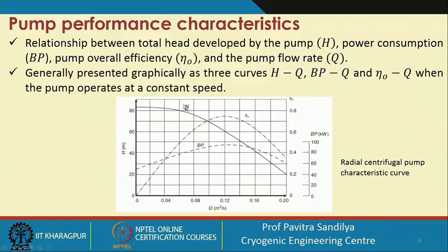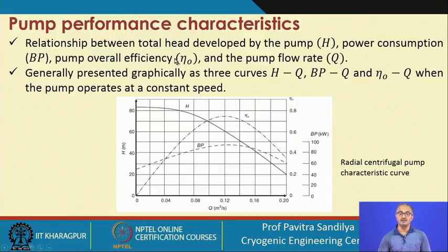Now we need to know the pump performance characteristics — the relationship between the total head developed by the pump, the power consumption, the overall efficiency, and the pump flow rate. When we correlate the energy given to the pump with the head developed, the efficiency, and the flow rate, these are called the pump characteristics. They are generally given in graphical form, plotting head versus flow rate, power versus flow rate, and efficiency versus flow rate when the pump operates at a constant speed.